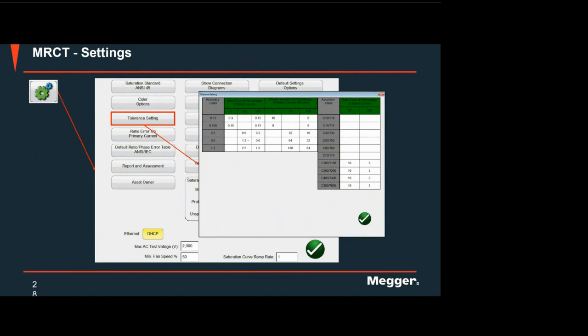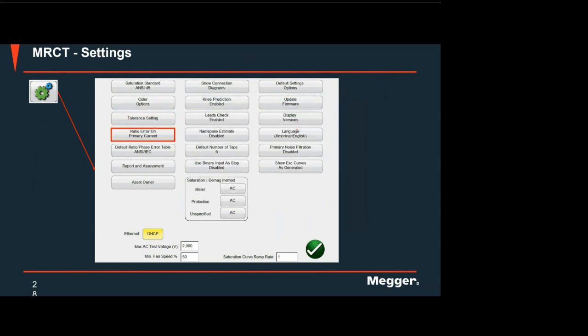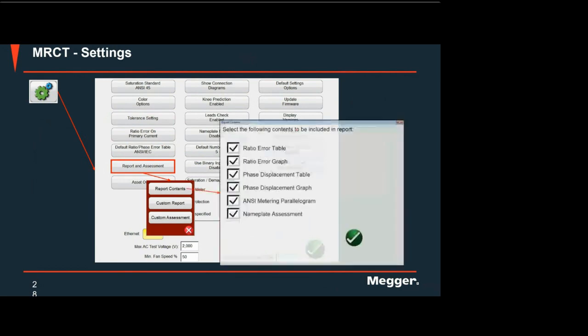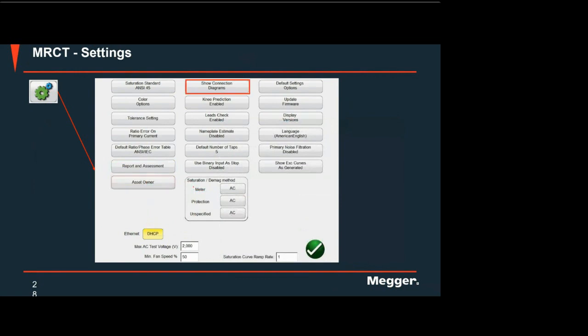And the good thing with the MRCT is that it has an automatic assessment whether the CT passed or failed the limits according to the standard. So it will display pass if it passed according to the standard and fail accordingly. Also, you can change the ratio error on primary or on secondary. You have the report assessment, so you can select what you want to see in the report: the ratio error table, graph, the displacement, etc. Okay, and of course, the good thing is that it will show you the connection diagram, so you can double check if your connection is correct.